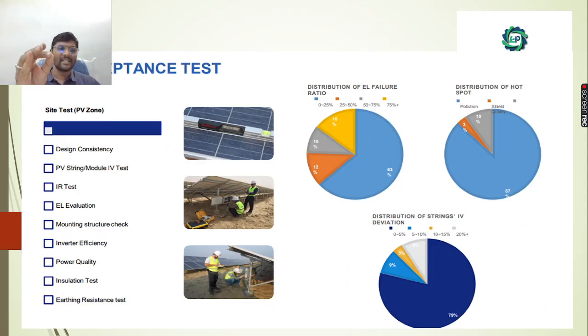Next, in the acceptance test in the site zone, we might be testing the design consistency, whether it is as per the design. We need to do the PV strings and module IV test, the IR test, and the EL evaluation. We need to check the mounting structures, whether they have been installed and grounded properly, and check the inverter efficiency, whether it is performing well. We also need to do the power quality analysis, the insulation test, and the earth resistance test.